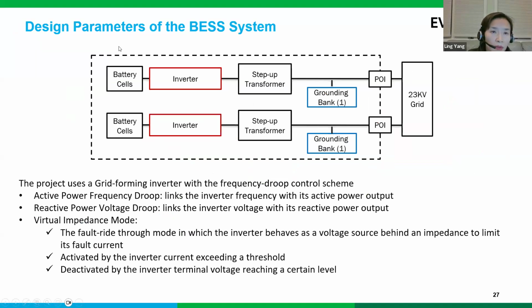This provides some of the schematic of the battery site. This is the 23 kV grid. We have basically 2 symmetric buses at the side, connecting through the battery cells, the inverters, and the step-up transformer, and between the step-up transformer and the POI, each part also has a grounding bank.